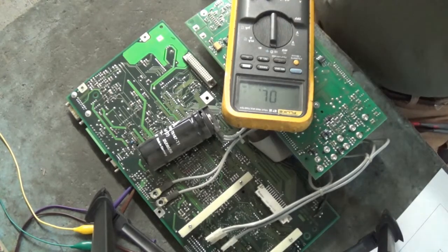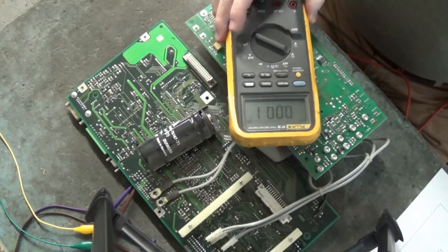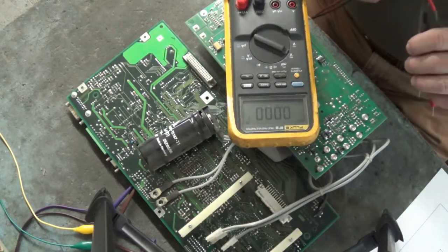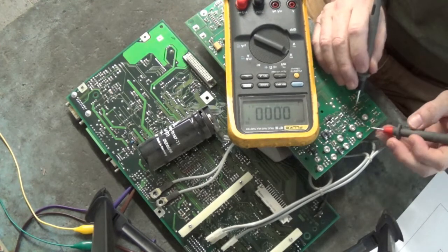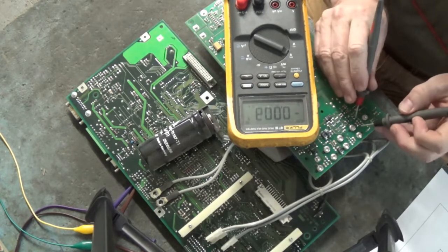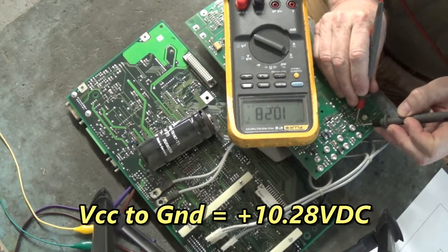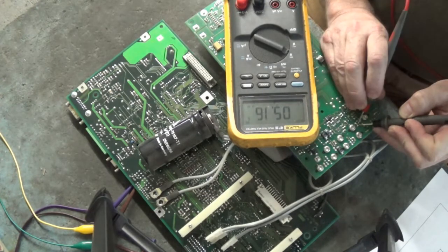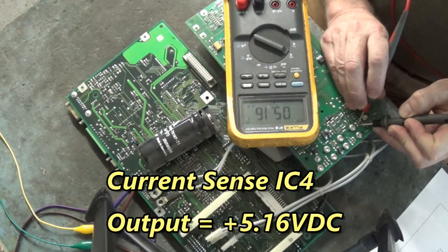Now we're going to take a look at the four current sense output voltages to see if anybody's different. Can you all see that okay? Here's the first one, that's VCC to ground, 10.28 volts DC. Here's the output, 5.16 volts DC.